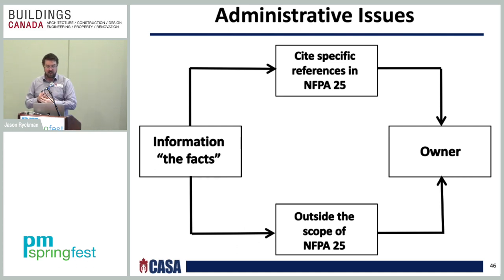Some administrative issues that come about. One of the things that everyone needs to come to together with, all stakeholders, when dealing with the inspection, testing, and maintenance, is communication, okay? The owner may not know what the inspector's telling you, right? The inspector, most of the times, is an ex-installer or has the water-based fire protection system type of lingo, which the owner may or may not understand what they're talking about. So it's key to have some good communication and the contractor having the proper wording to use to the owner so the owner understands what the installer is saying, and also the owner kind of knowing their system a little bit better as well so they understand a little bit better. It's all about communication. It's all about information, okay? With that information, it's fact, okay?